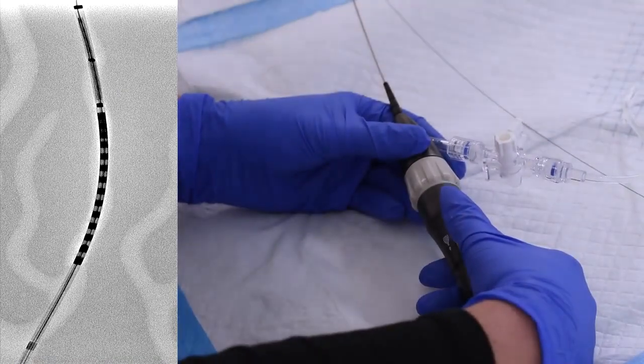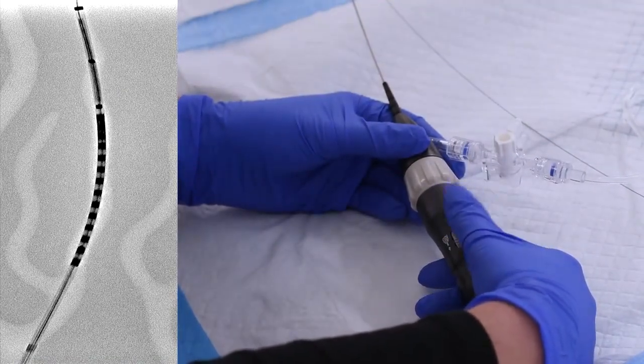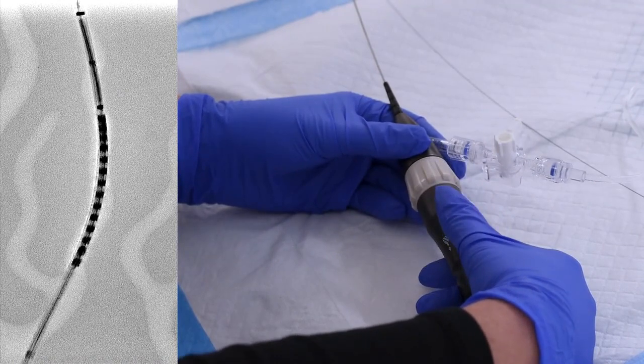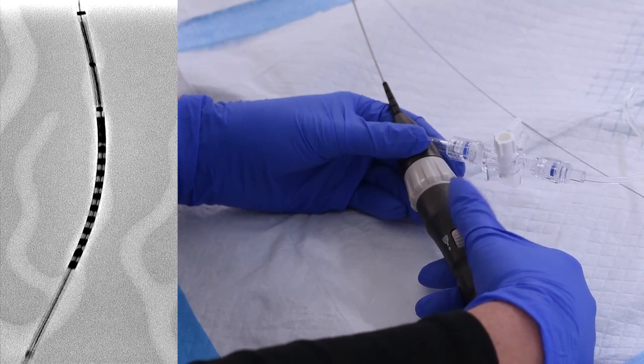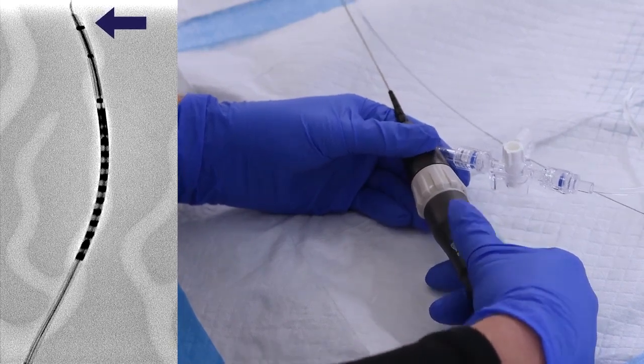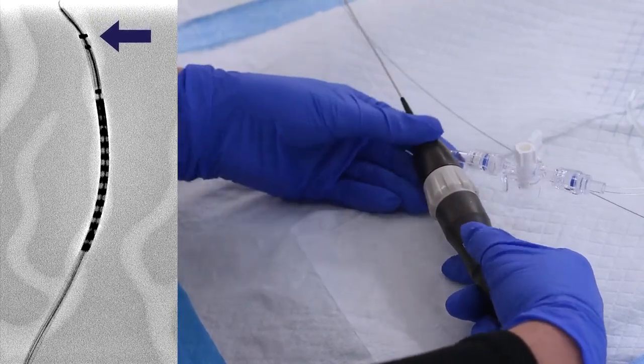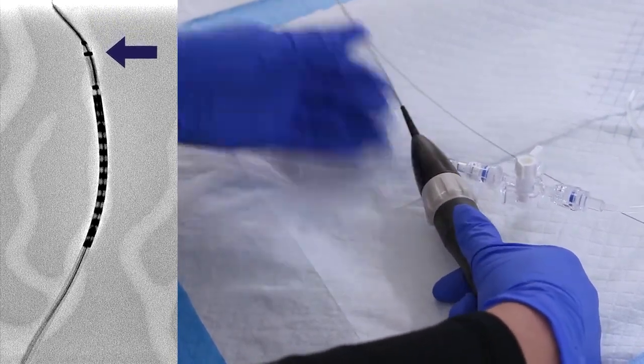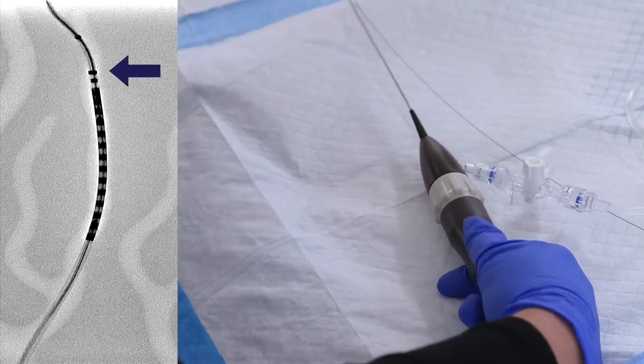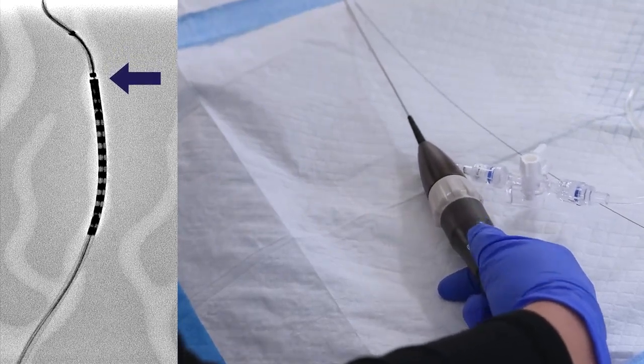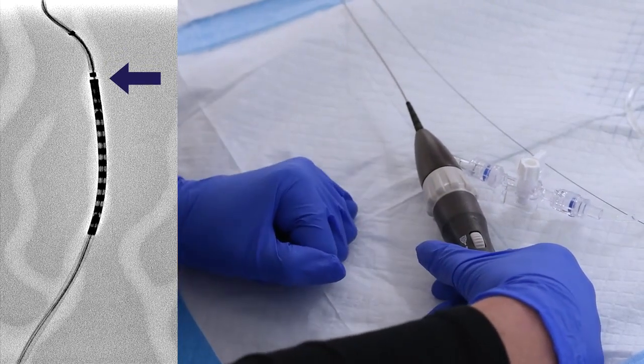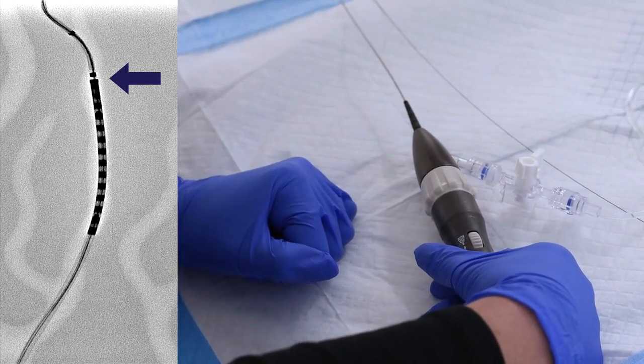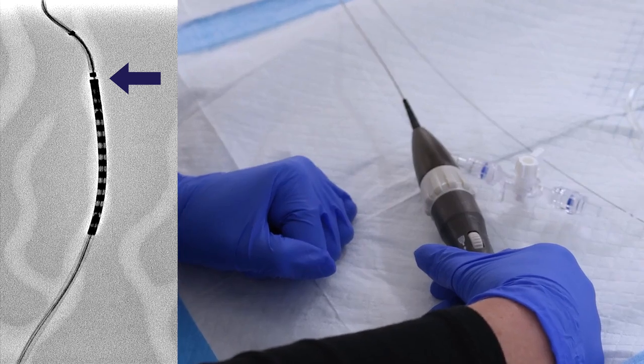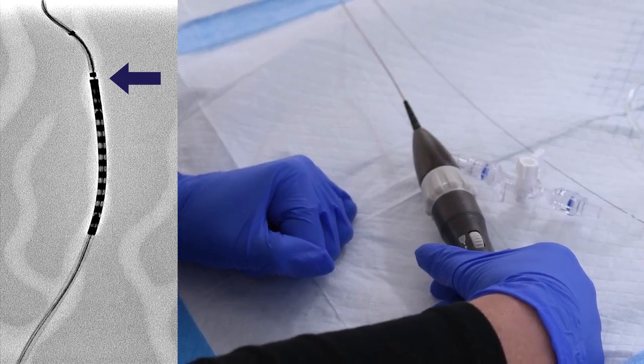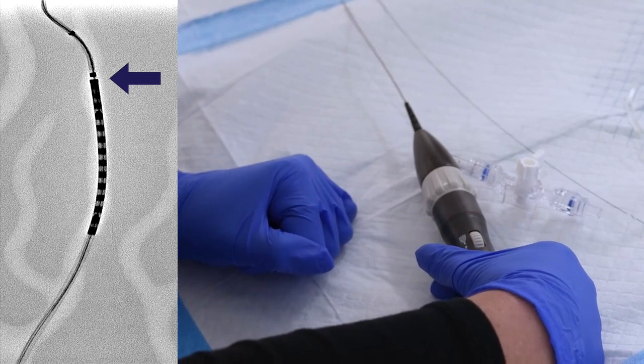Slowly retract the outer sheath by rotating the thumb wheel towards the proximal end of the handle. As the outer sheath retracts, audible clicking will be heard. In addition, a radiopaque marker on the distal end of the outer sheath will be visible during retraction of the outer sheath. Retract the outer sheath until the radiopaque marker at the distal end of the outer sheath is positioned below the bottom of the filter and above the stent. We would see this superimposed with the proximal end of the filter and the distal end of the stent. The filter will be fully exposed at this point and can be deployed.